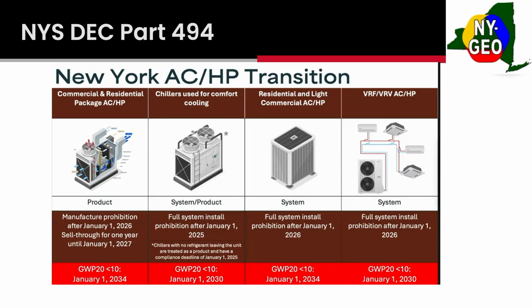So here's the VRF. And then the big story here also, if you look in the red here, New York has a tighter deadline for ultra-low GWP. So what's that ultra-low GWP? We're talking R290, propane, refrigerants like that. And we're not ready for that. In 5 years, are we going to be ready to put R290 propane in our buildings? I highly doubt it. We're getting there, but we've got a ways to go.